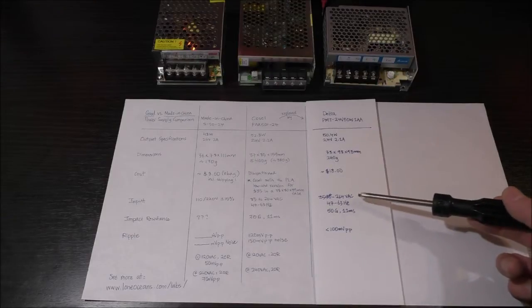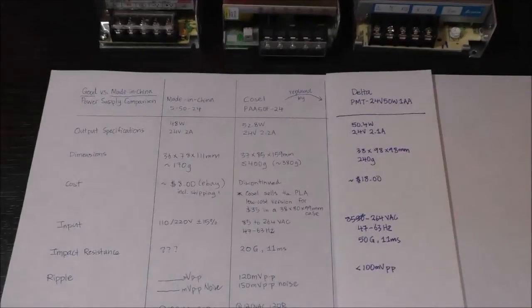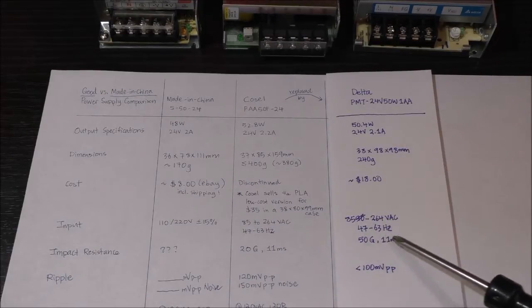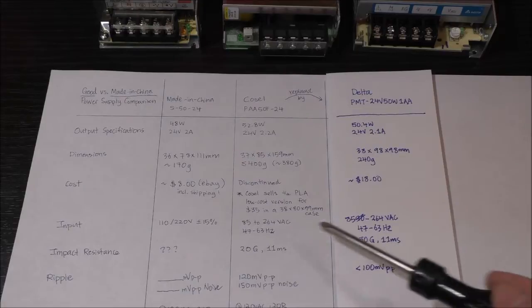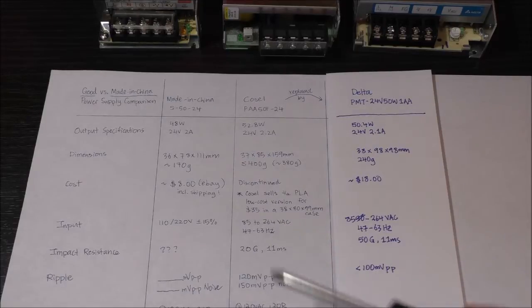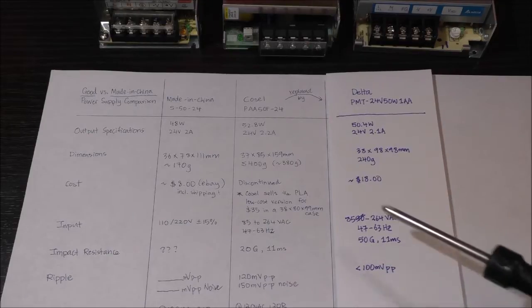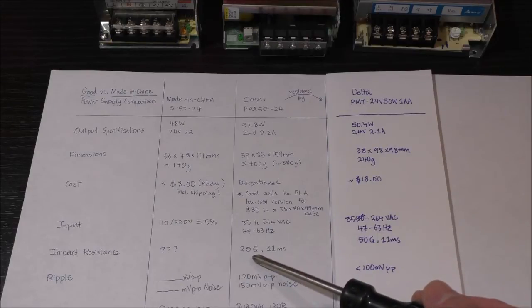As for the input rating, we can see that the Delta power supply is rated for 85 volts to 264 volts input, 47 to 63 hertz, and that is identical to the CoSel power supply. And according to the data sheet, it's actually capable of withstanding 50 Gs of impact for 11 milliseconds. And in this respect, it's actually better than the 20 G rating of the CoSel.